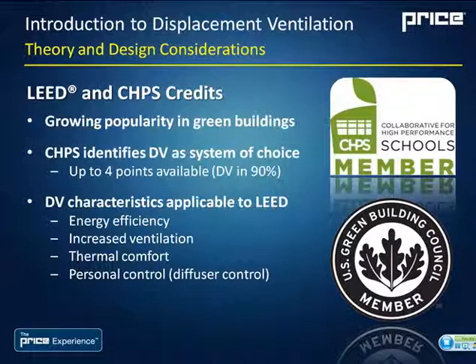As well, there's the LEED program, which has a variety of credits that displacement ventilation could be applied to. The first would be the energy efficiency, the increased ventilation rate. As I mentioned, there's a LEED credit for increasing your ventilation rate 30% above ASHRAE 62. So if you're already getting almost a 20% discount with the displacement system, it's much cheaper to obtain that credit with a displacement system than it would be with a mixed system.